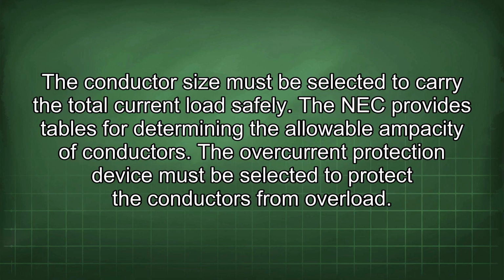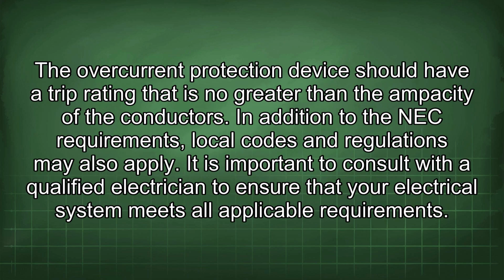The conductor size must be selected to carry the total current load safely. The NEC provides tables for determining the allowable ampacity of conductors. The overcurrent protection device must be selected to protect the conductors from overload. The overcurrent protection device should have a trip rating that is no greater than the ampacity of the conductors. In addition to the NEC requirements, local codes and regulations may also apply. It is important to consult with a qualified electrician to ensure that your electrical system meets all applicable requirements.